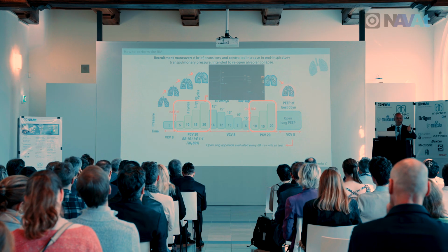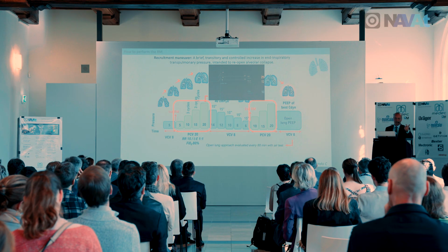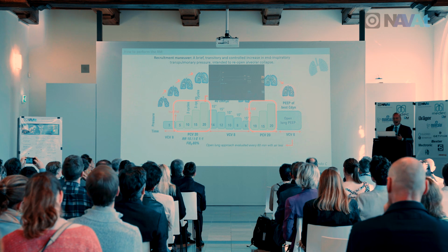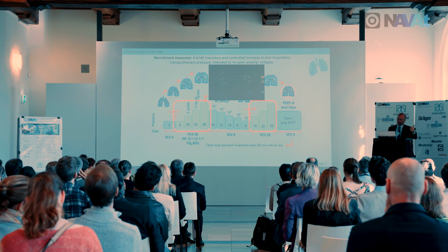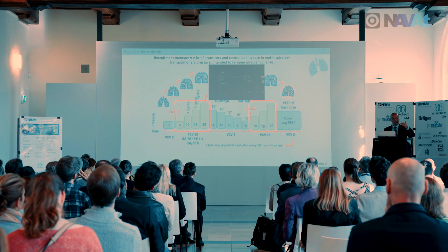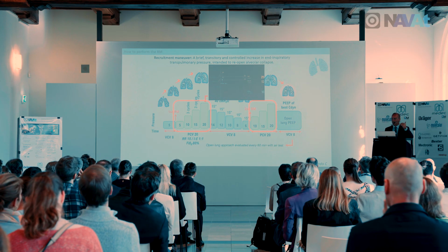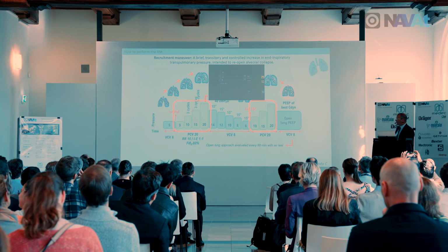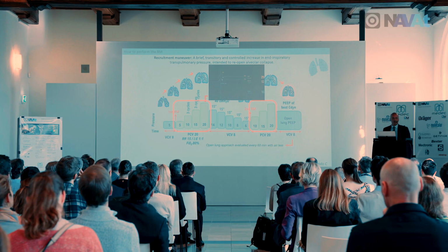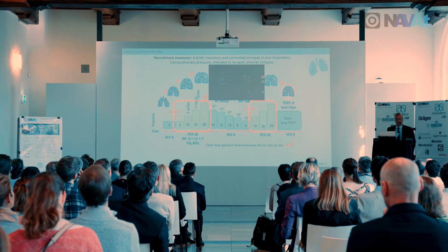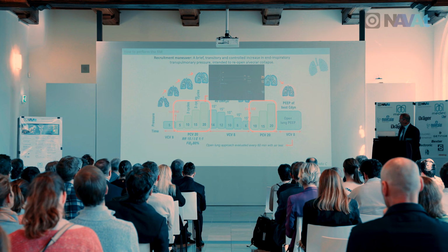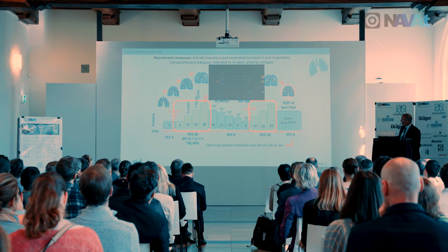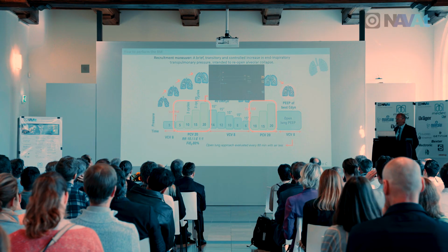It's easy to perform. In most of the newer anesthesia machines, we can program this maneuver. It's hemodynamically better tolerated than most of the other recruitment maneuvers that have been proposed, reduces the risk of biotrauma, and it's a really short maneuver. In less than 1.5 minutes, you perform this recruitment maneuver. You can see with this screenshot of an anesthesia machine how we perform it.